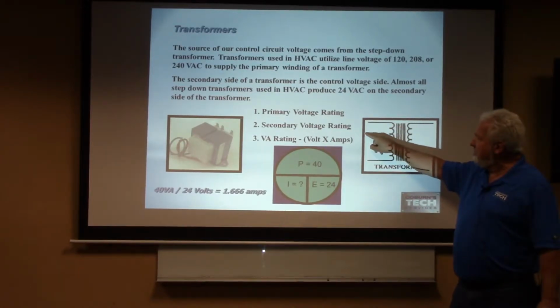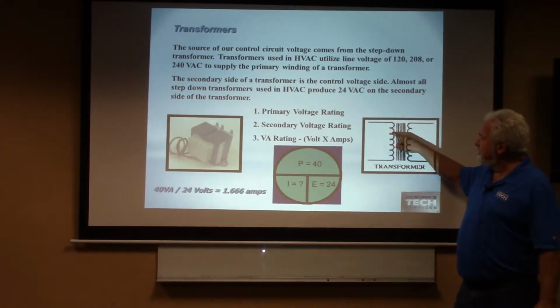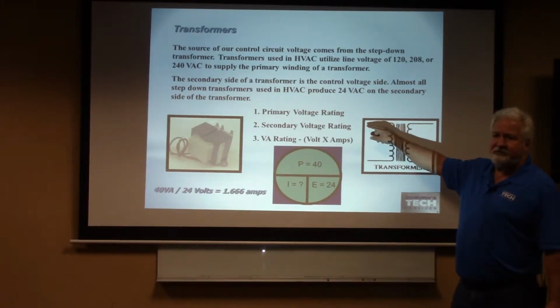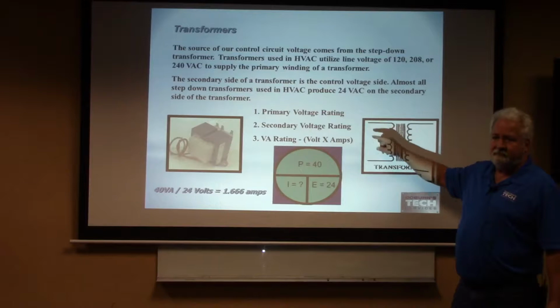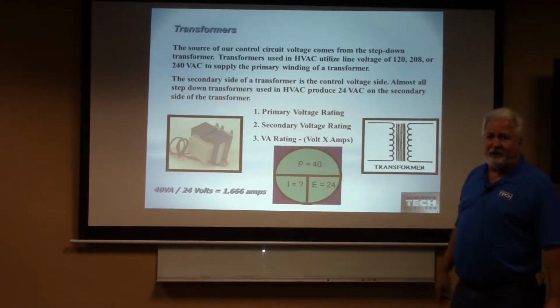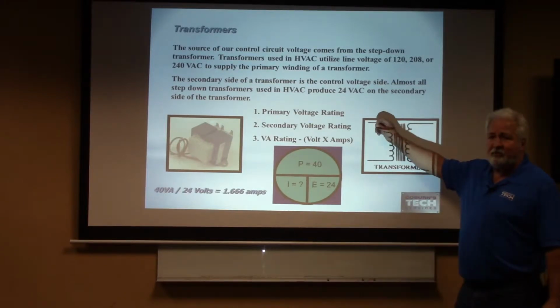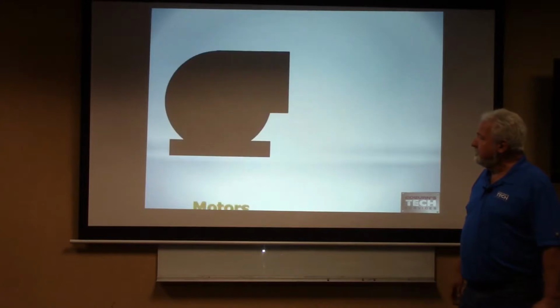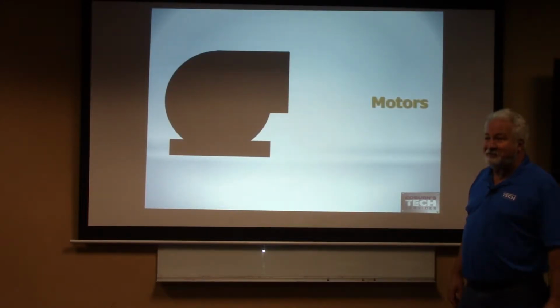If I applied voltage here to go to here, would that voltage still come out this side? What do I need to do with that? Just tie it off or just cut it off or what? I need to wire nut it off because I still have voltage coming out of there. Is that right? Good. So I do need to wire that off. I can't just tie them all together, can I? No, let's not do that. All right, good. All right. Yeah, let some smoke out.